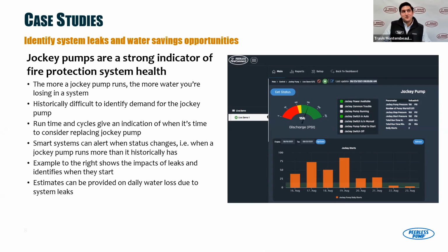One of the things we've learned with FireConnect by crunching all this data that we see in fire pump rooms, because for the longest time, we knew there was plenty of information there, but we didn't have a good way of getting it out and analyzing it. And this is probably obvious to some of the seasoned veterans in the fire protection world here, but the jockey pump is the item that runs basically constantly in a fire protection system, especially compared to your fire pump, which only runs for a weekly or monthly test unless there's a fire. That jockey pump gives you a really good picture of system health, and changes to jockey pump performance over time really give you an indication of when things can change within your system as well.